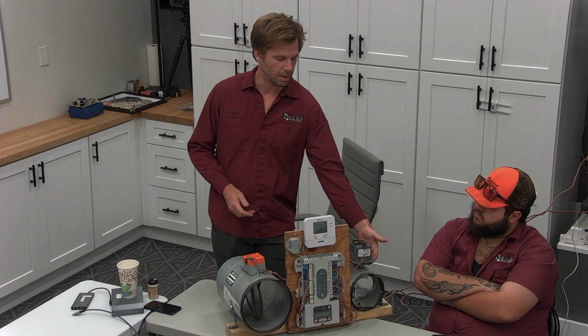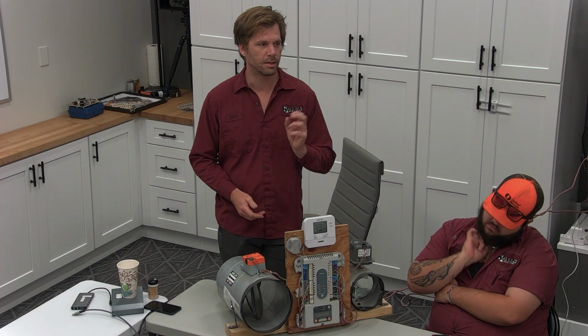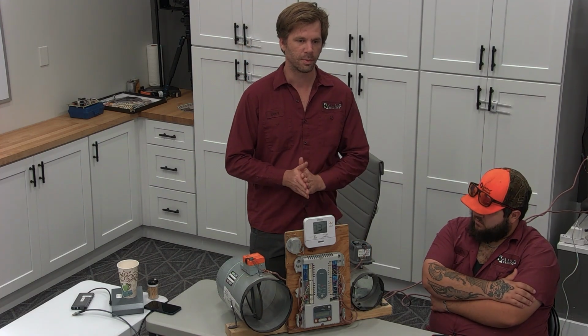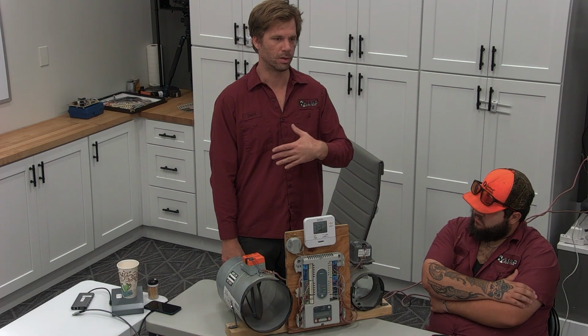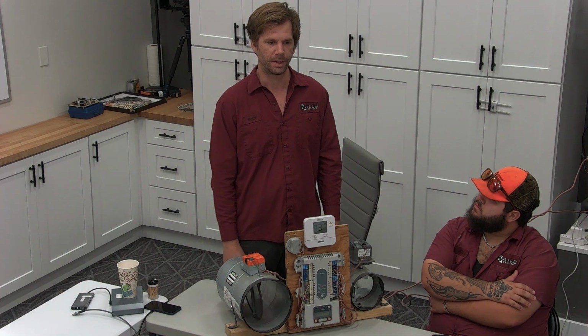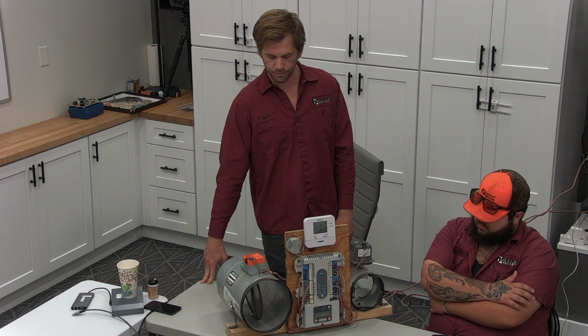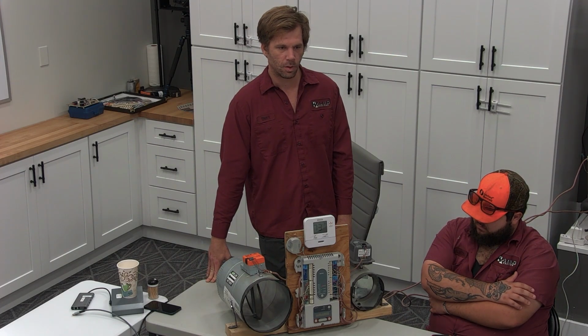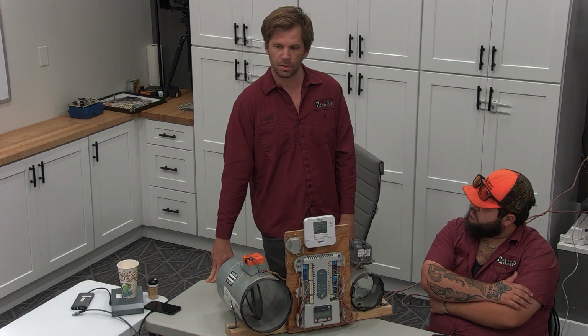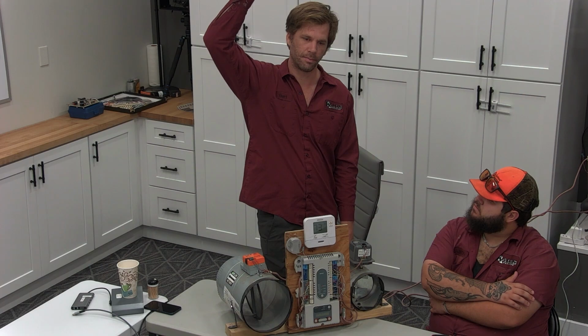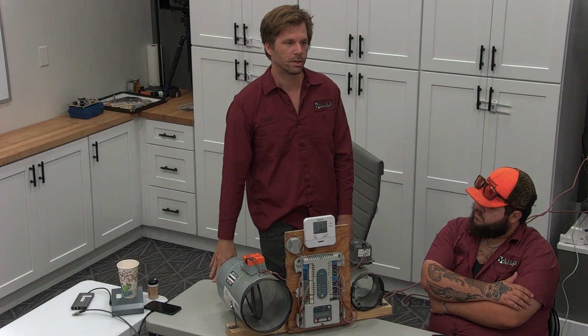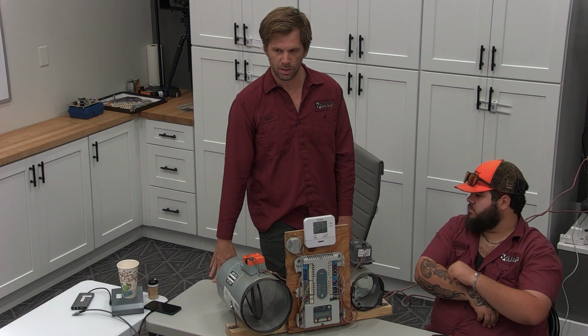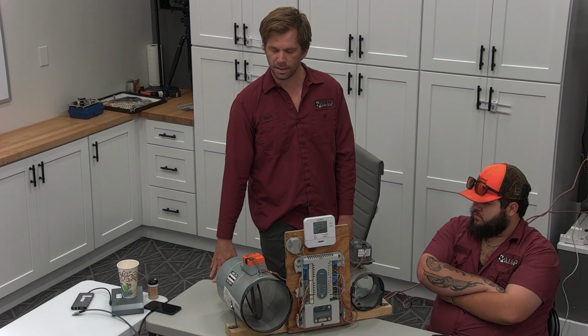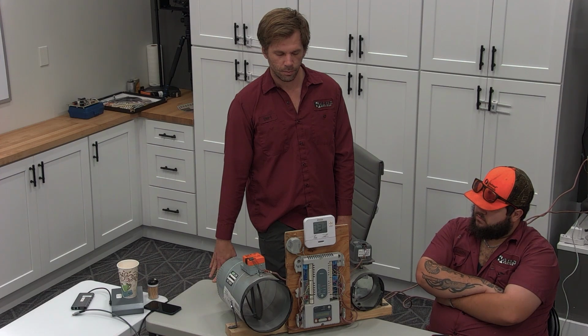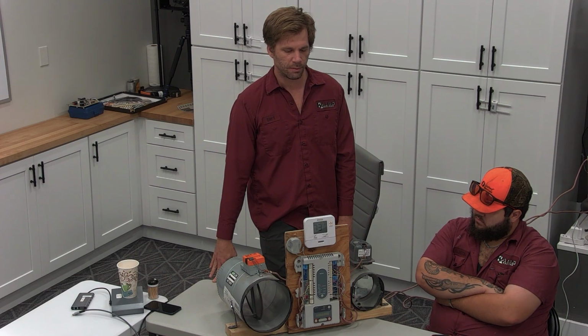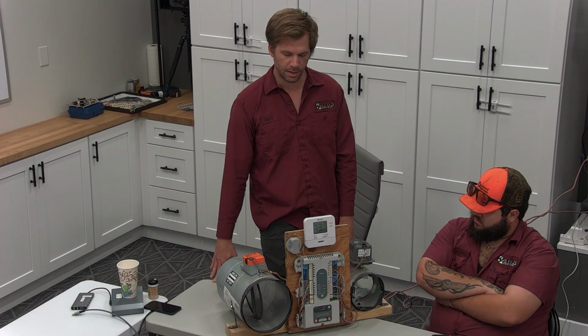Your motor's spinning, but the set screw that is supposed to be tightened to the shaft is loose. So the motor's spinning, but the damper's not. Typically the airflow will push that damper closed and the motor will spin open and nothing will happen. So even if you're in the attic, you don't see that unless you open the ductwork. But if you're down in the home and you turn on that thermostat and the airflow doesn't come out, you already know what's going on before you get up there. And you know when you actually need to get up there. There's a lot of time that can be wasted assuming that there are difficult problems before you've checked the most basic. So that's what that is.